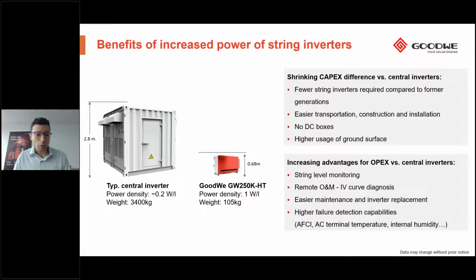And we're going to address here a bit a topic which sometimes in the EPC and developer community is an ideological, emotional one. Sometimes it is string versus central inverters. Of course, every technology has advantages and has a big community which is supporting it and thinks that that's the better technology. But overall, it's a solution. And what we are seeing with the trend of increasing power in our string inverters, and that's what you see on the pictures, now in a much more compact size, we are able to pack a much higher power density. So compared to a typical central inverter, which packs about 0.2 watt per liter, we pack 1 watt per liter in the volume of a string inverter, so 5 times higher power in the same inverter body.